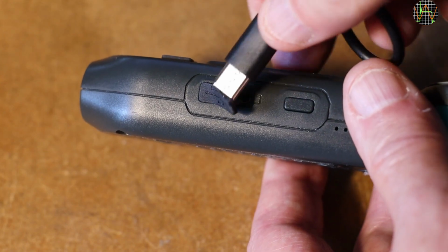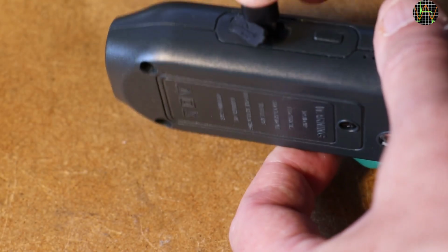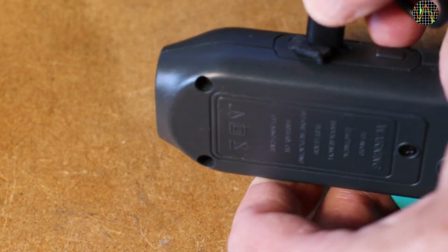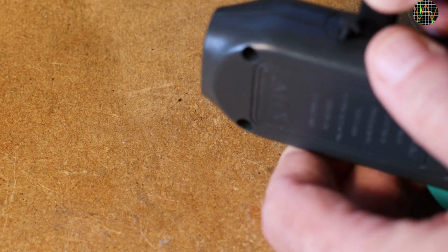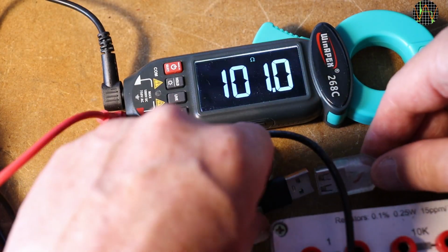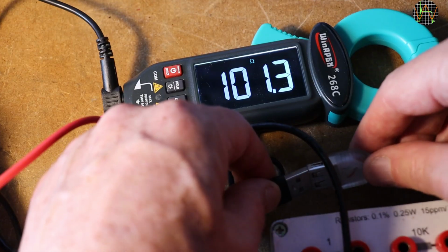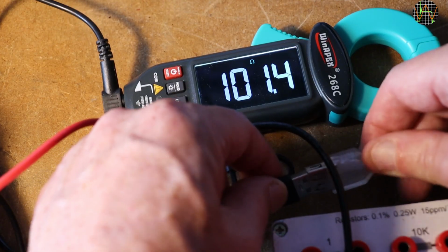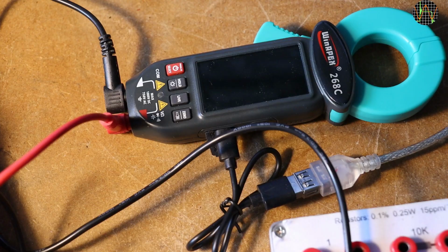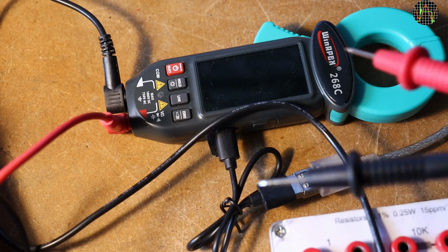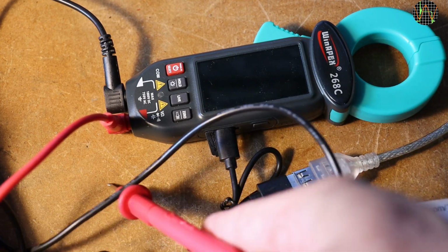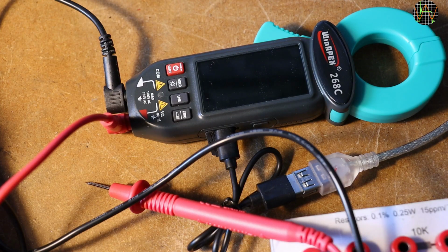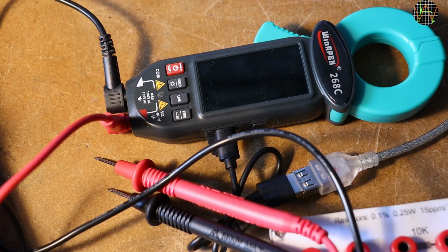While we are at the subject of safety, this meter is charged via a USB-C port at the side. This is potentially very dangerous if the meter is used at the same time for measurements. At least they thought about this problem. Watch what happens when you plug in the USB lead into a charger, or in this case an extension plugged into a charger. With a click, the meter turns off and remains so until you unplug the charger. That makes it impossible to do measurements while charging, which is good.